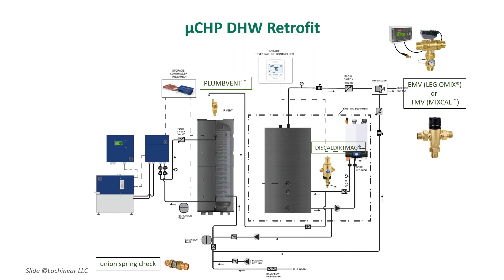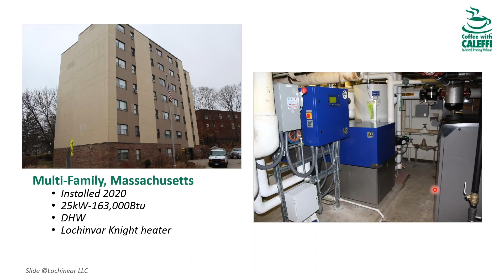Another example here, you can see how compact the system is, with the backup heater on the right. Again, these units are very compact, that's why they're called micro. Easy to maneuver in, doesn't take up much room. Having a backup heater, we use the cogen to charge some tanks and provide base heat, and rather than having the boiler modulate as often as it normally would without a cogen, we're just pulling it in for peak demand.